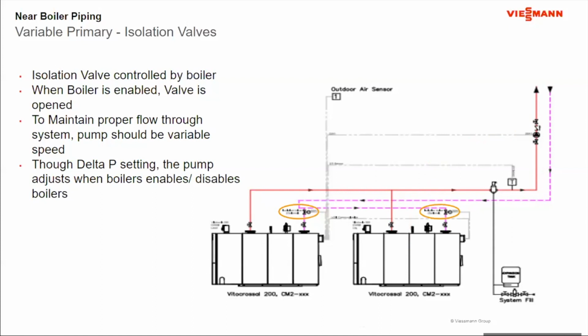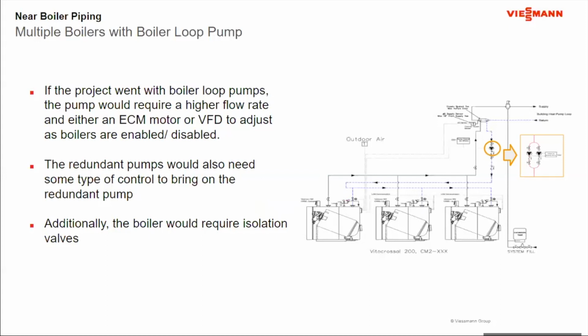Okay. Now, when I go to primary, secondary, from an isolation standpoint, I have 2 options. I can either do a pump for the boiler loop, or I can do individual boiler pumps. A lot of times we'll see the request come in for an individual boiler pump. In reality, what usually happens is this individual boiler pump actually becomes a pair of pumps because of redundancy. So I'm going to have a pair of pumps out here in most cases when I have multiple boilers, from the aspect of redundancy. So I'm going to add a pump and put an isolation valve at each boiler. Because of these isolation valves, I want this pump to be running off of an ECM motor or a VFD so that when boilers are brought in and out of the circuit, the pump will adjust.